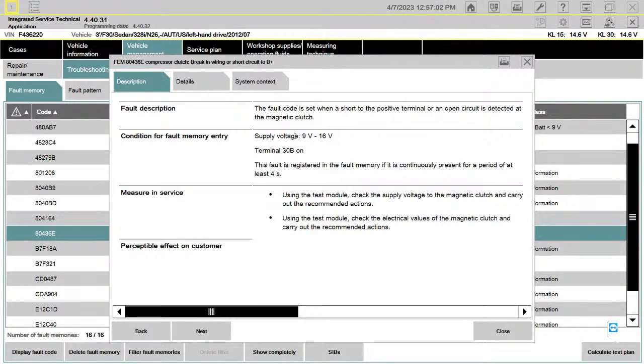The enable criteria for that: 9 to 16 volts, terminal 30B on, meaning the ignition is in the run position. The fault is registered in the fault memory if it's continuously present for a period of at least 4 seconds. So it's not some little blip, it's happening for at least 4 seconds.